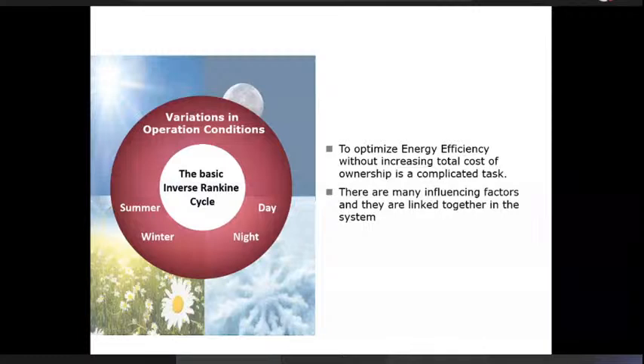Same thing at night, the temperature has gone down, so we can also bring this closer to the ideal inverse Rankine cycle. So these opportunities show up because we move to a technology which is not a fixed on-off type of compressor, but a variable speed compressor. Now, when we are adjusting the compressor speed, we also need to match the pressure drop on the other side, and for that reason, we must have some means of a continuously adapting expansion device.